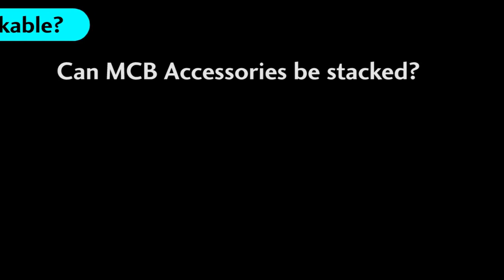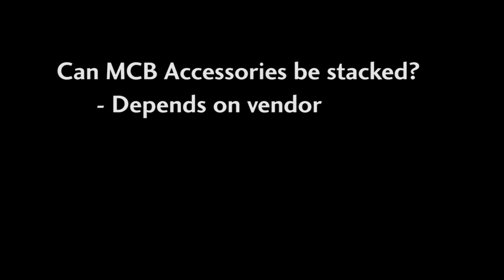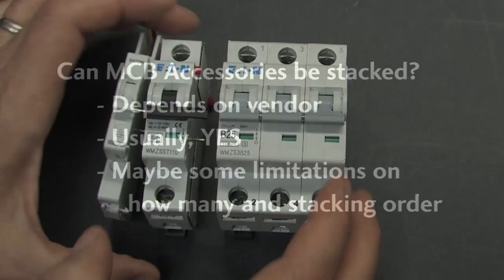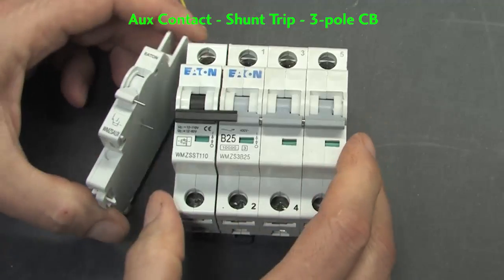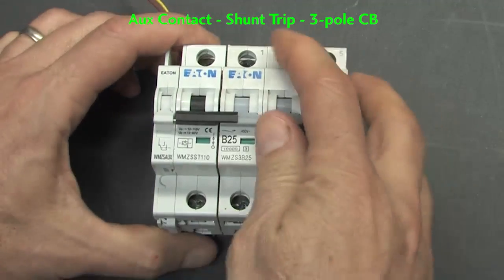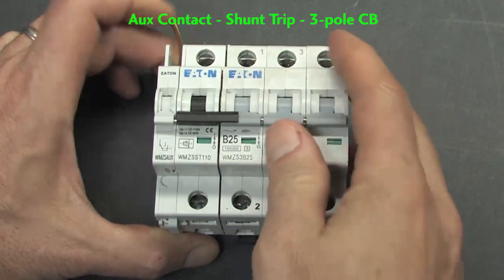Can you stack these MCB style accessories? Well, it depends on the vendor but usually the answer is yes. For example, here is a shunt trip and an AUX contact stacked on a 3-pole breaker. Now we can remotely trip the breaker and monitor its status.